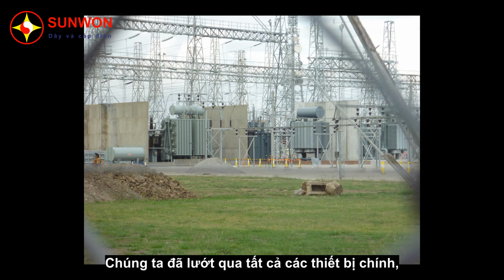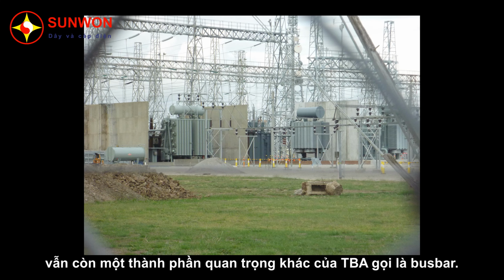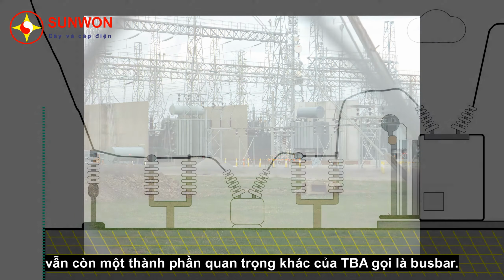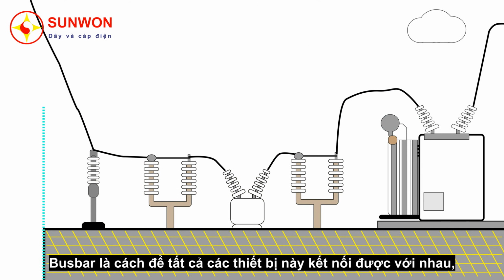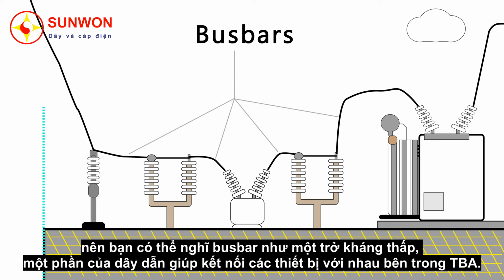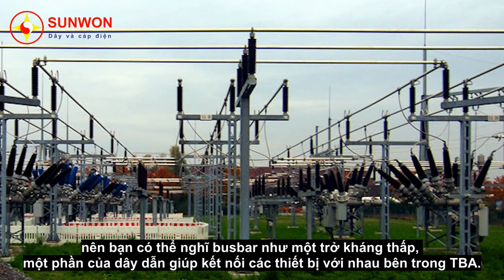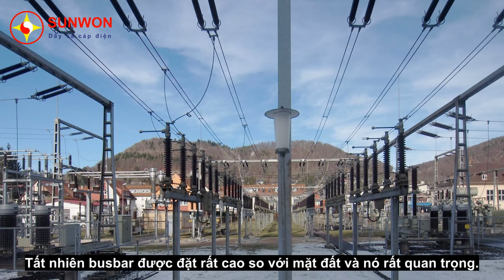So we've gone through all of the main assets now. There is one other important element of the substation called the bus bars. The bus bars are the way that all of these assets are connected together. You can think of bus bars as just a low impedance piece of metal which connect assets together within the substation. Obviously, these bus bars are very high above ground, so they're at a safe level, but they're also very important.